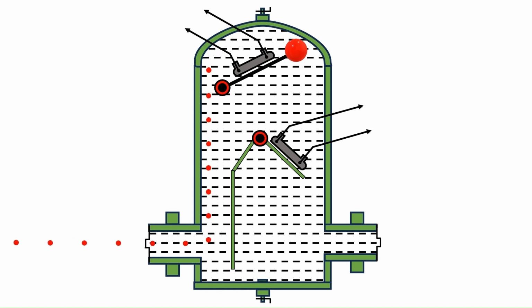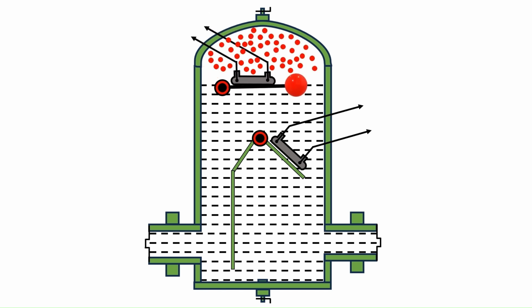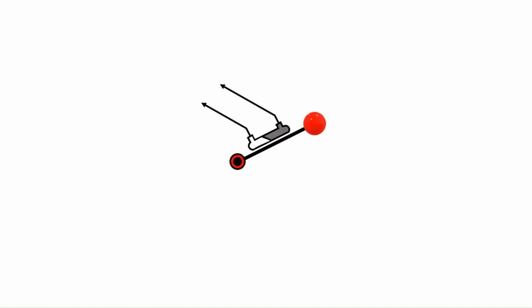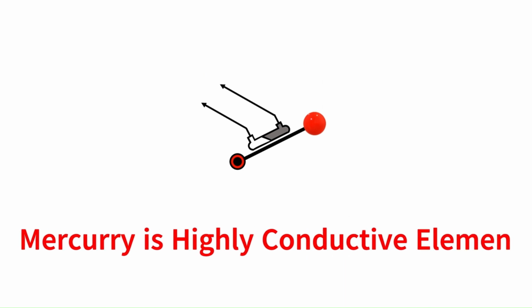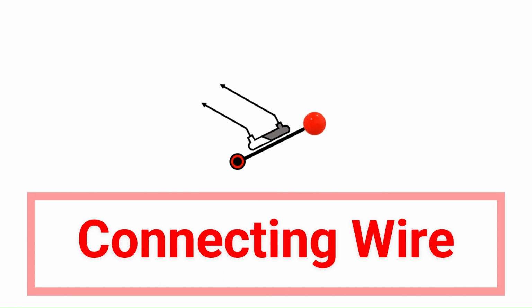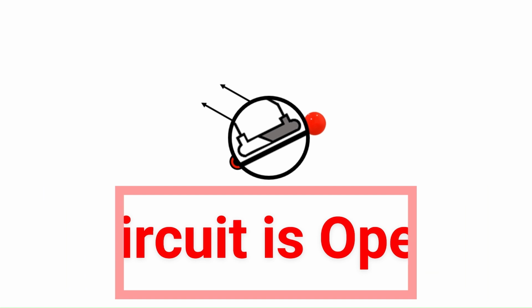Due to accumulation of the gases, oil level in the Buchholz relay starts reducing and therefore the float will also tilt with reduced oil level. Mercury is a highly conductive element. In a mercury switch, it acts as a connecting wire. At the time of normal condition, the mercury inside the switch is not connecting both the contacts. So, the circuit is open. When the float tilts after the fault, the mercury switch also moves. Therefore, mercury connects both the contacts and the circuit closes. Therefore, it will give an alarm to the operator.